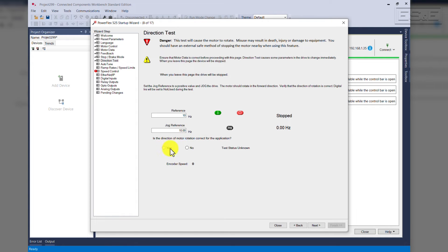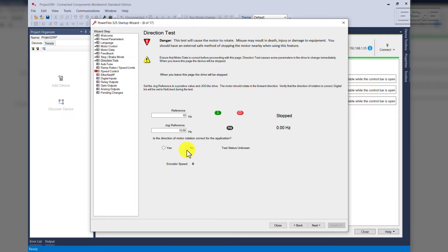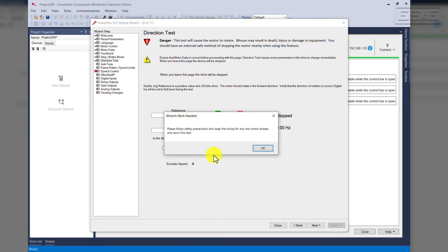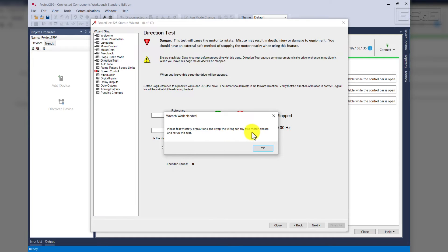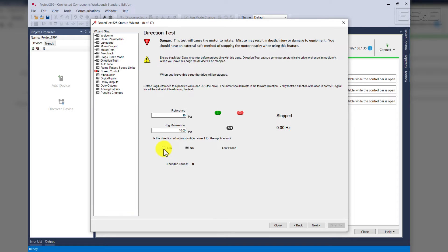Please observe the rotation of the motor, because you must make a decision on the direction of the motor and can make changes. I press Stop. The question down here, is the direction of the motor rotation correct for the application? If it says No, we'll click that. Please follow safety precautions, swap the wiring for any two motor phases, and re-run this test. If I select Yes, test has passed. Press Next to continue.